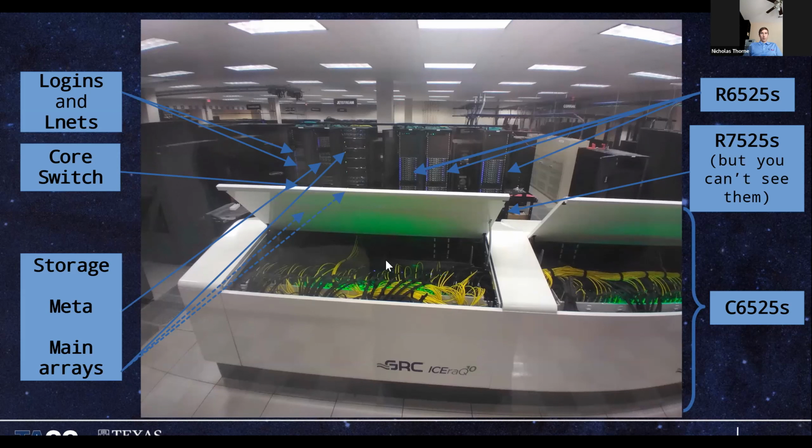I said I'd bring up Lone Star 5 again. Where these tanks actually are located is where Lone Star 5 was before we removed it. It was a Cray system, and Cray are pretty famous for creating very good density of servers in an air-cooled environment. The way they do this is they control a lot of the airflow, and they use essentially the equivalent of in-row coolers. You can see we've got a pair of in-row coolers in the background over here. You can see that, yes. So we're using similar technologies to what the Cray did in the air-cooled environment.